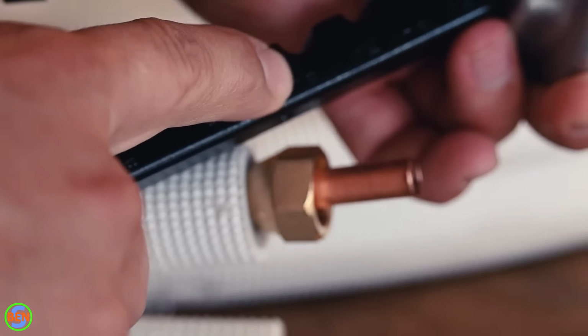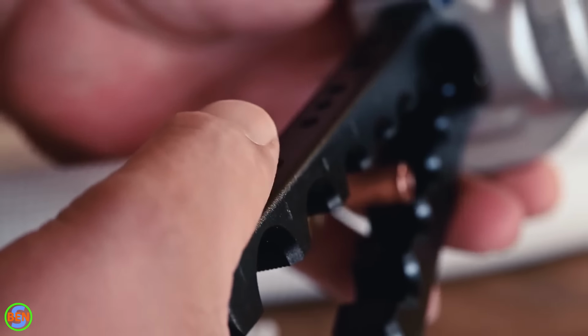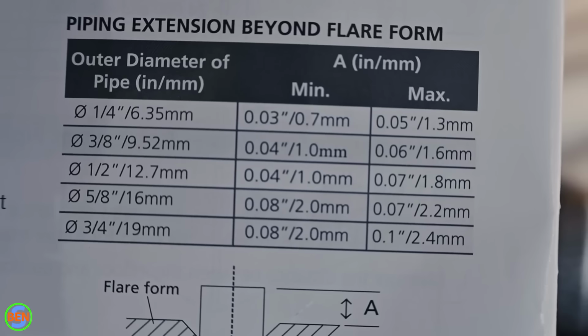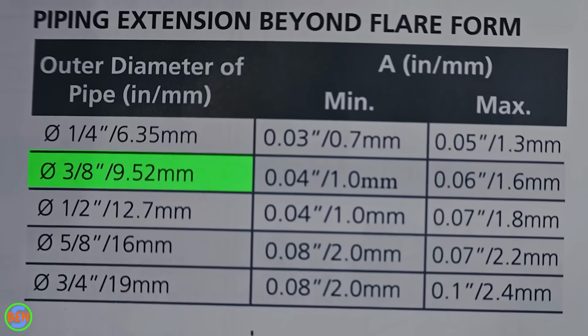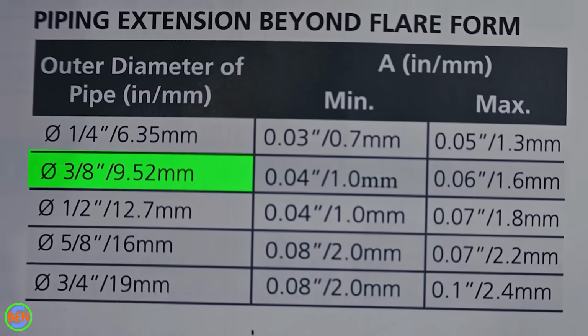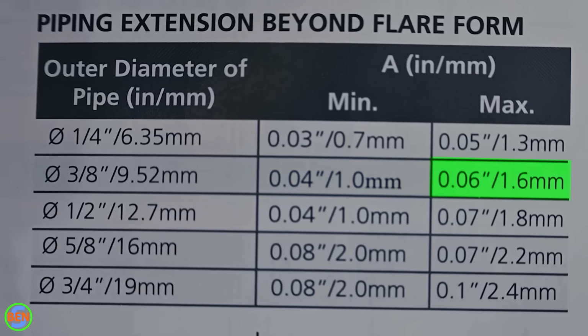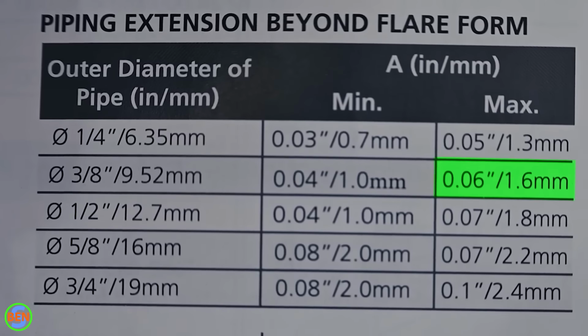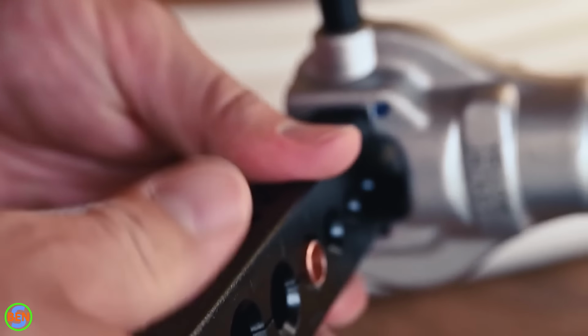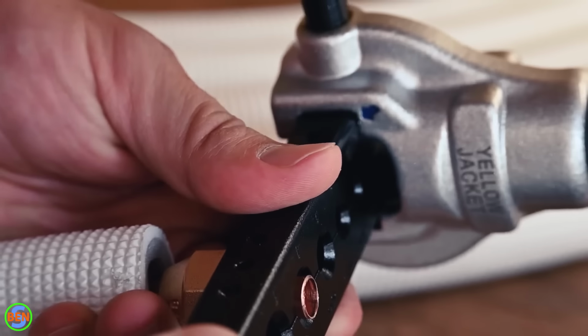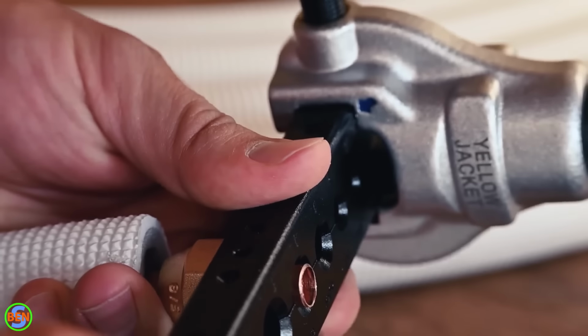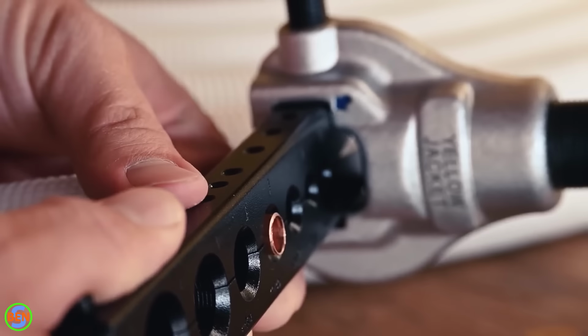Now that we've got the inside of our copper tube reamed out, we're going to clamp the 3/8 size over the end, and we want to let that extend out just a tiny bit. Here's the official recommendation for 3/8: they want it to be anywhere between 1 millimeter and 1.6 millimeters above the face of the tool. So now that we know that, we want it to be 1.6 millimeters at the most, which comes out to be close to a 1/16. Right about there looks good.